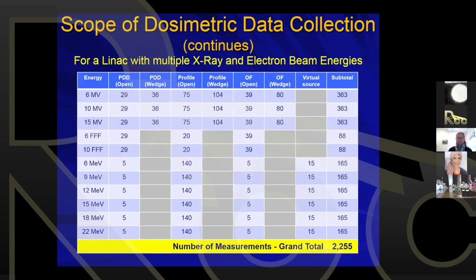If other machines can only produce, say, 2 X-ray beams and maybe just 5 electron beams, potentially the commissioning can take less time. So it is dependent on the number of beams that you have, and of course, whether you are going to be utilizing all the beams or not. Some centers don't use any of the electron beams, just the X-ray beams. So that would reduce your commissioning time.